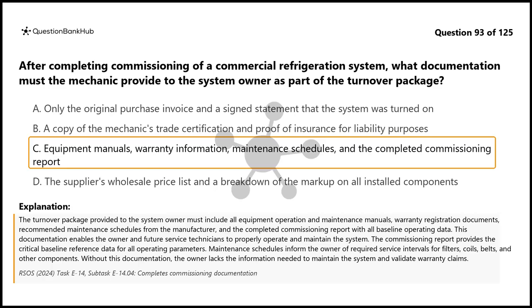The commissioning report provides the critical baseline reference data for all operating parameters. Maintenance schedules inform the owner of required service intervals for filters, coils, belts, and other components. Without this documentation, the owner lacks the information needed to maintain the system and validate warranty claims.